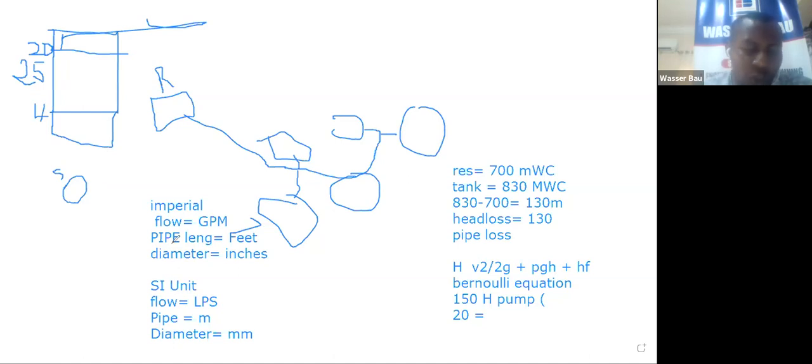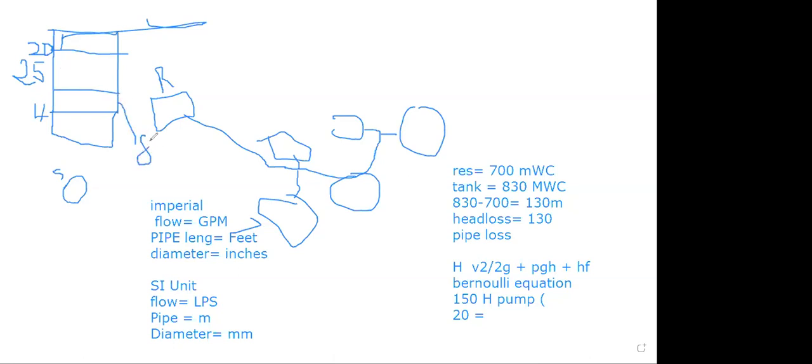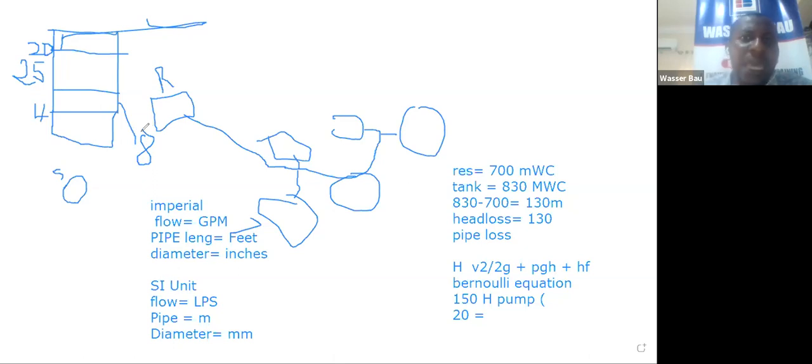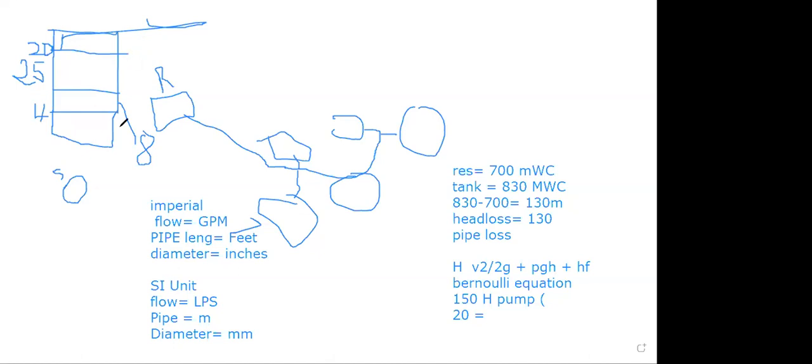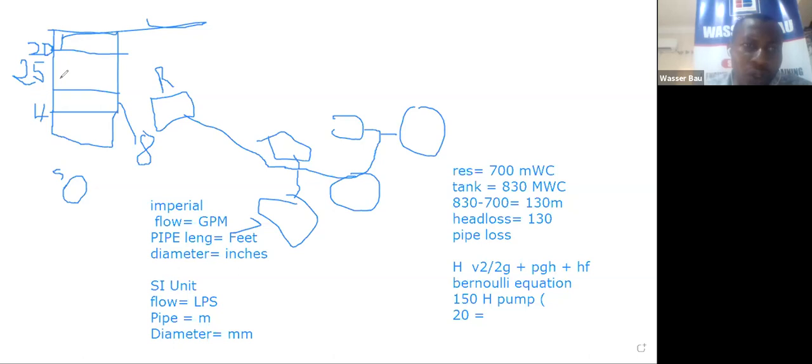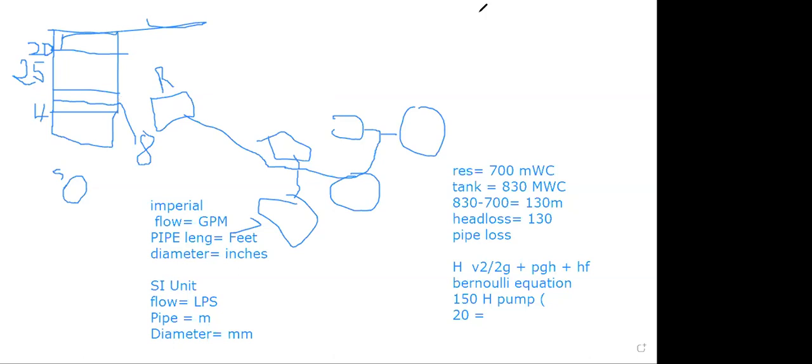In Abuja, for instance, let me share this with you. The water that's supplying Gwarimpa, if it gets to a certain level, some areas in Gwarimpa will not see water. Because the tank they are using now to supply Gwarimpa is not the tank that is meant for Gwarimpa. The tank that is meant for Gwarimpa is still being built. Some of us that live in Abuja see that they are trying to resume work on the tank that was supposed to supply Gwarimpa. So they are using a tank that is meant for another district, and that tank is not high enough. So each time the water level goes down to a certain level, people will have water stress. In some areas in Gwarimpa, the water pressure will be abysmal.